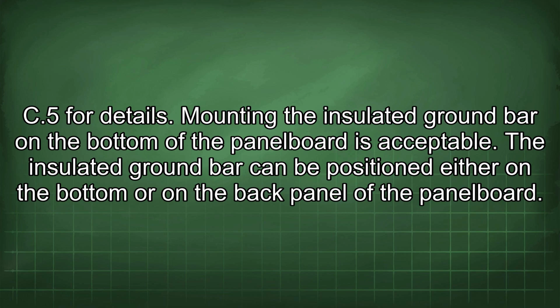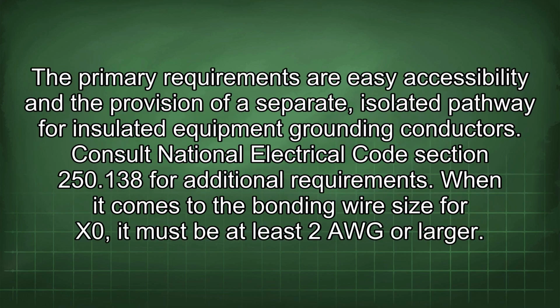Mounting the insulated ground bar on the bottom of the panel board is acceptable. The insulated ground bar can be positioned either on the bottom or on the back panel of the panel board. The primary requirements are easy accessibility and the provision of a separate, isolated pathway for insulated equipment grounding conductors. Consult National Electrical Code Section 250.138 for additional requirements.